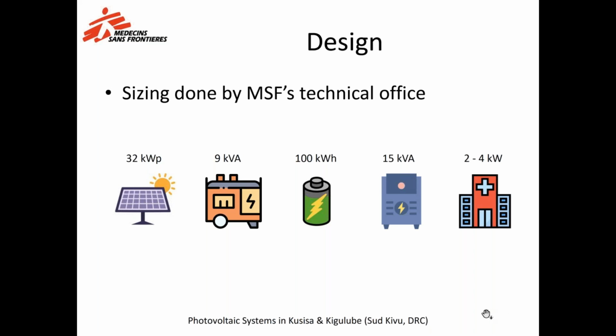So we went for 32 kilowatt peak photovoltaic modules. Each hospital had 2 generators of 9 kVA each, which were only acting as a backup power source. We installed a 100 kilowatt-hour battery bank and a 15 kVA charger inverter. All this system is for a hospital that is consuming between 2 and 4 kilowatts.